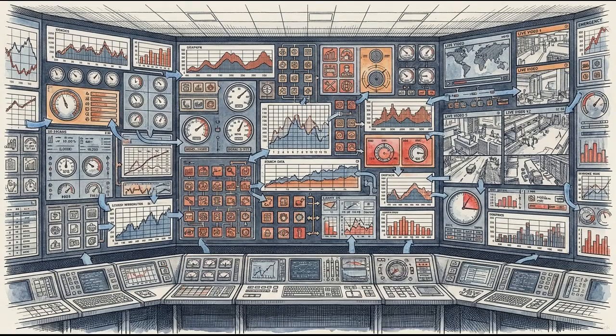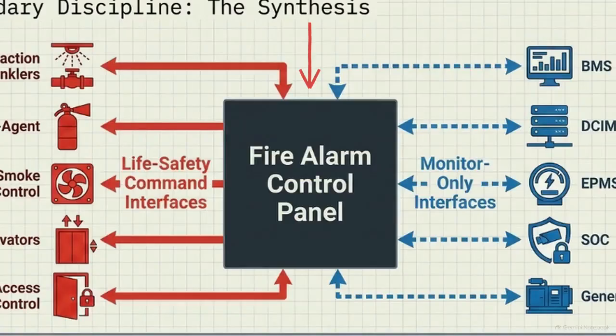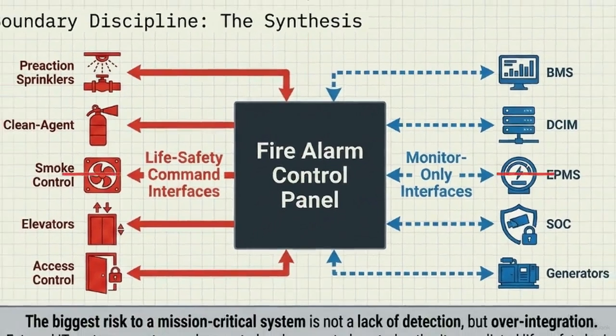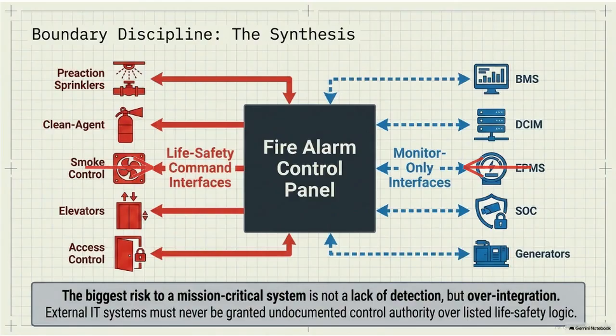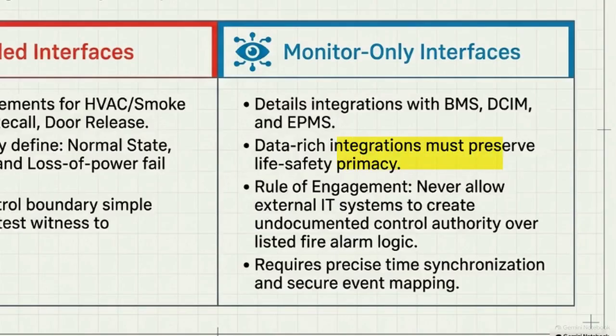There is a common desire in facilities management to merge every building system into a single dashboard for convenience. Over-integration is the highest risk to the data center. A defensible design uses the FACP to separate red life safety command interfaces from blue monitor-only interfaces. External IT systems must never be granted undocumented control authority over listed life safety logic. These rules of engagement allow external systems to observe data from the network while preserving life safety primacy. They can pull information, but they are never allowed to execute commands.